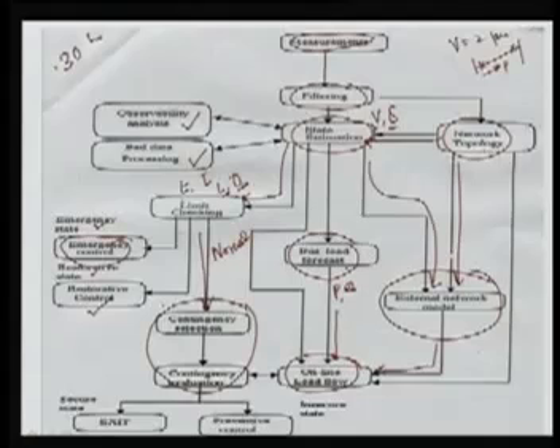So this is the information that is required for your online load flow. We know in the load flow analysis, we require the real power and reactive power information at the buses, and at the same time we require the network topology that is coming here, and we require the external network, and then we can run the load flow that is used in the contingency evaluation process.